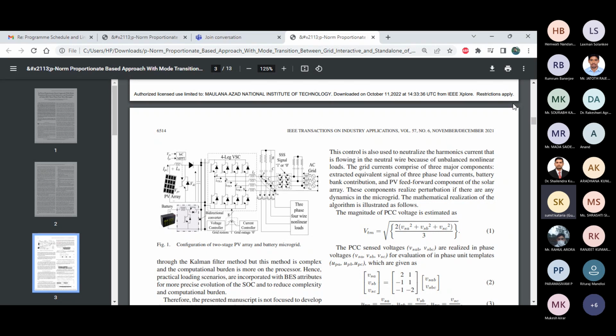So 40% capacity is not utilized when we are having only grid connected converters. How we can utilize this 40% capacity of the inverter so that the utilization factor of the system can be increased? Here we have one VSC connected with the PV array as well as battery storage, and then connected with the AC grid.